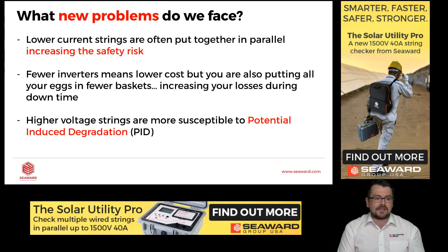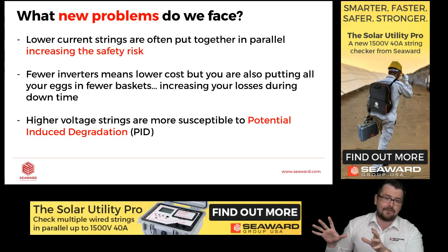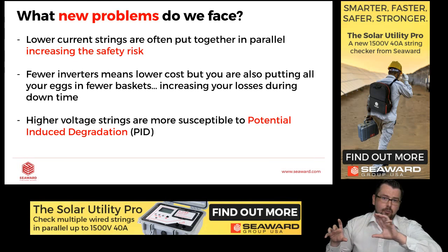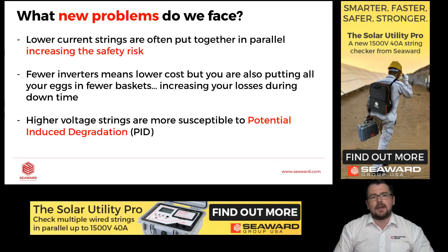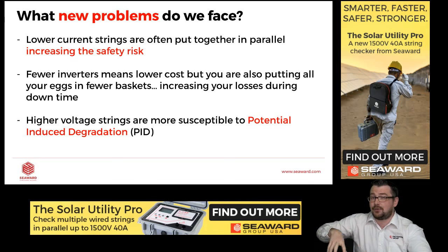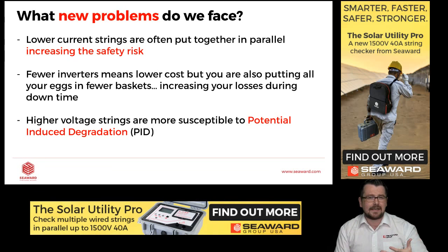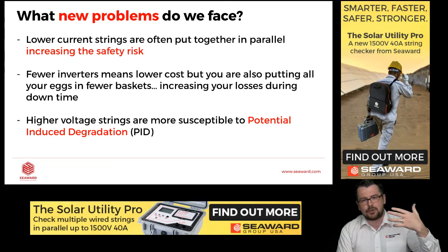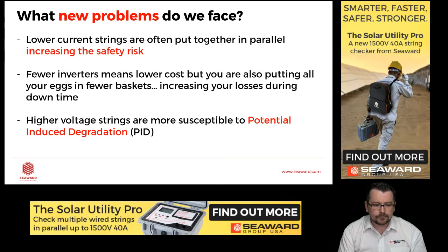I mentioned on the previous slide that if we have fewer inverters, we're lowering the cost. But overall, we're putting our eggs in fewer baskets. So that means we're increasing the losses during our downtime. So if one of the bigger inverters goes down rather than one of our single little inverters, then we've lost the whole generation. So that is a consideration, particularly for inverter manufacturers, to increase their reliability.